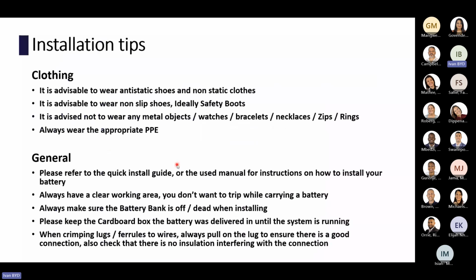In terms of BYD installation, it's always advisable to wear anti-static shoes or safety boots, and please don't wear any metal objects that can short things, and wear appropriate PPE. Please always refer to the quick start guide, the quick install guide, and have a clear working area without any slippery surfaces. You don't want to trip when carrying a battery. Please make sure the battery is off or dead when working on or installing it, and please keep the cardboard box until the system's up and running, because if there's an issue, which is rare, the battery has to go back, and then it's easy to ship.